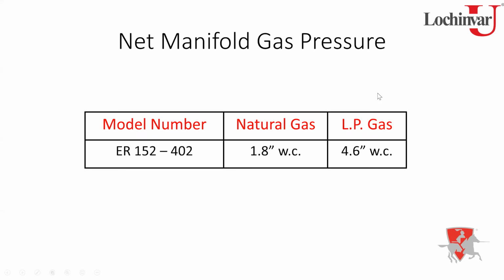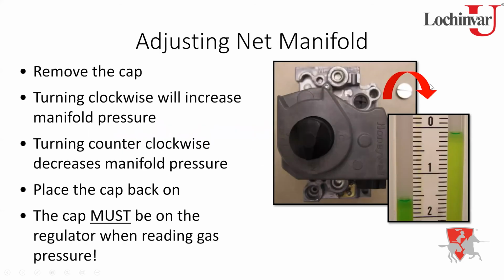So to adjust the regulator while the heater's running, we're going to pull that cap off. Now, here's what's going to happen. When you pull that cap off the regulator, I'm taking that air pressure off of it. That manifold pressure is going to drop. You're not going to have enough gas coming through to sustain the flame. It's going to drop out. So if the heater's in operation, if the burners are running, the flames are going to go away at this point.